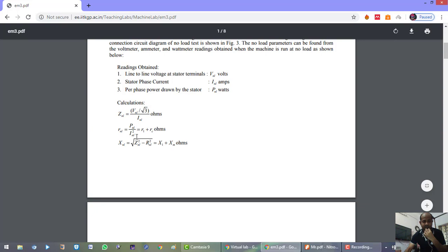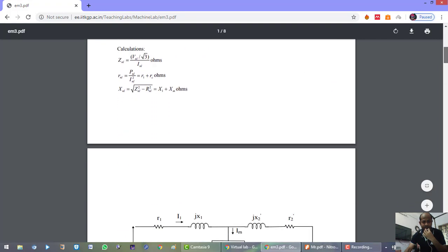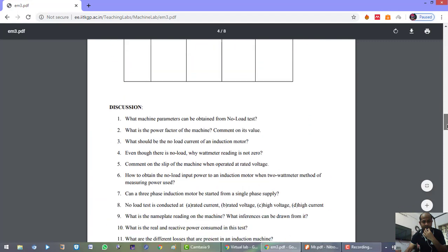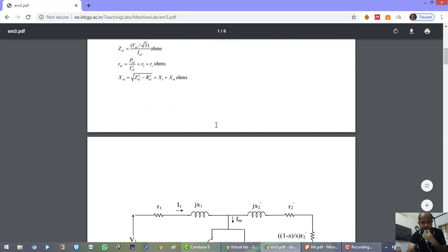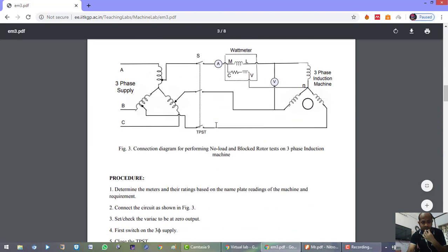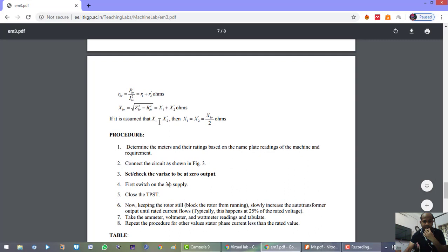If we get the impedance value, we can find resistance, since R equals P divided by I squared — that is the sum of stator resistance and rotor resistance referred to the stator. Similarly, subtracting R from Z gives us X. Using the thumb rule, we assume x1 equals x2, so x1 and x2 each equal x divided by 2, giving us all the series parameters.